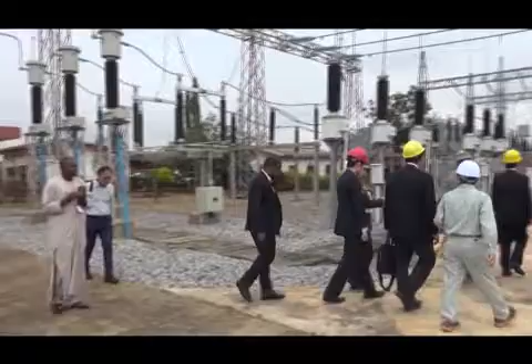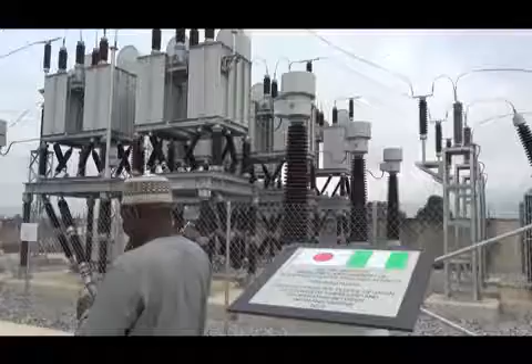Explaining the importance of the capacitor bank installed at the substation and another at Kefi substation of TCN, Mr. Yazu Yasuhi of Yachiho Engineering Company, the Japanese firm which handled the project, said these capacitor banks improve the voltage. When load is high, the voltage on the 132 kilovolt side goes down, so if a capacitor bank is installed, it raises the voltage, improving the voltage of this area.